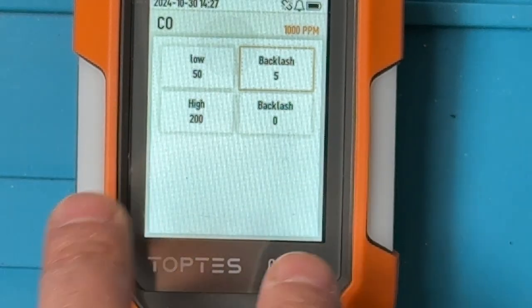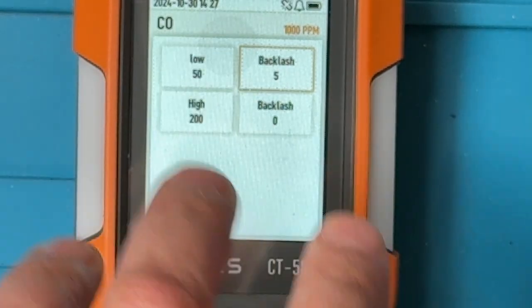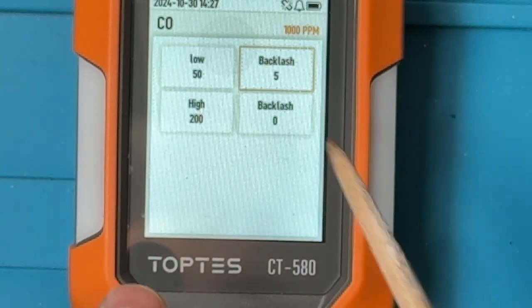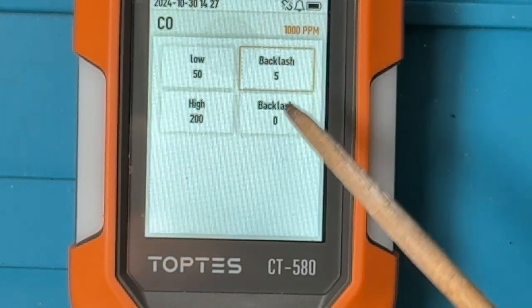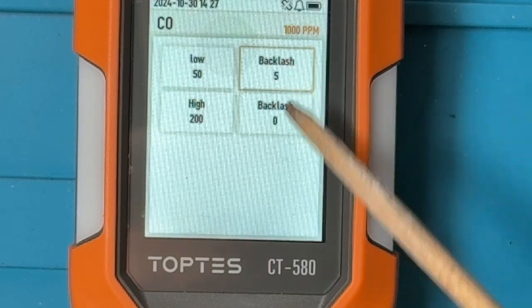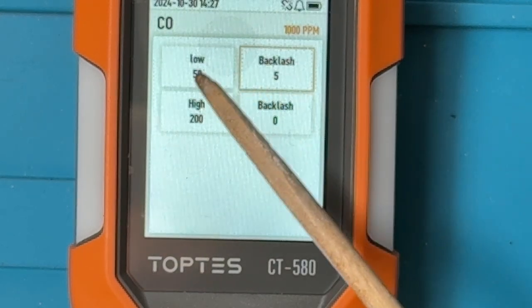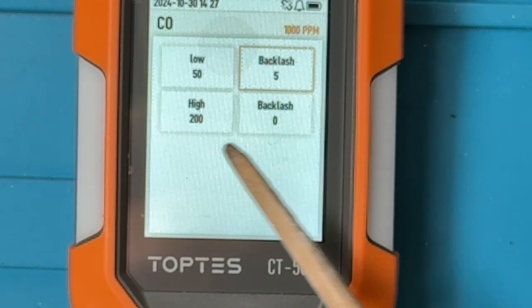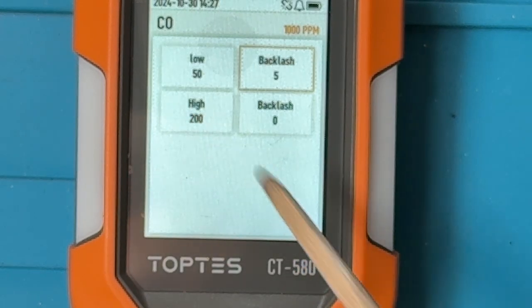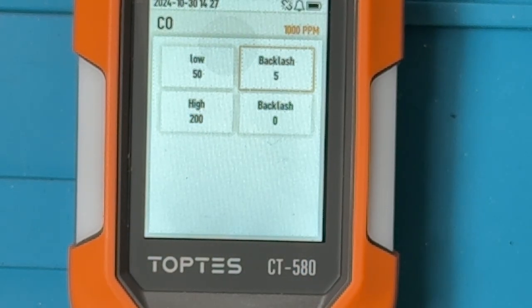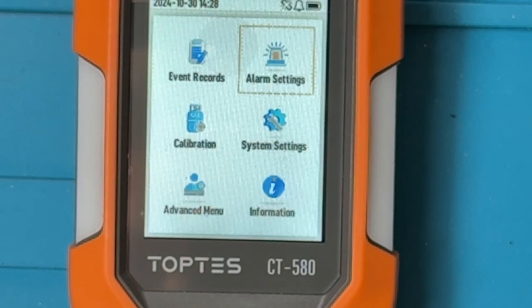And so the alarm will keep sounding until the concentration of carbon monoxide drops below 45 units. So that's what the backlash is for, and this one is intended to go with the low threshold. This one is designed to go with the high threshold. But both of them work in the same manner, in the sense that they define how many units below that upper threshold the concentration needs to drop before the alarm turns off. All right, so that's how the alarms are set.